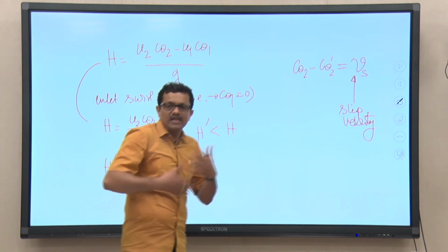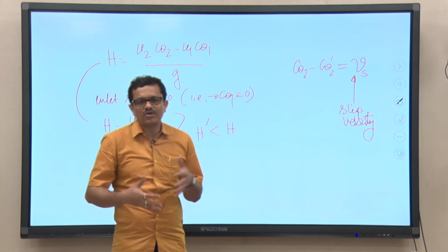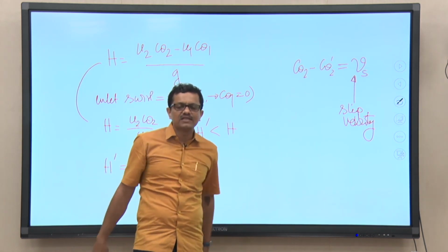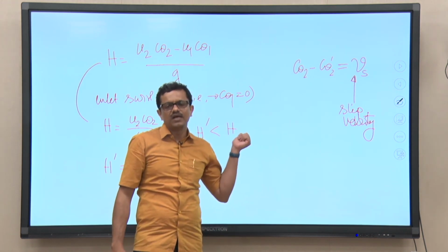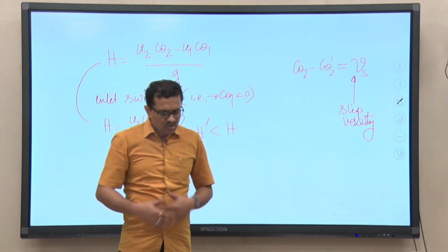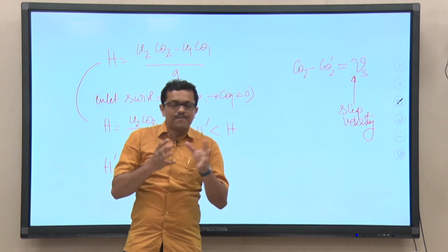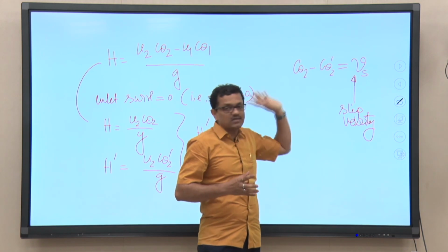So, we really cannot eliminate this, because that will be there, but our objective should be to design the pump in such a way that the slip component can be reduced, essentially to achieve a higher head. Okay. So, we will be discussing that now: the slip velocity, that is what we have predicted, is nothing but C theta 2 minus C theta 2 prime.